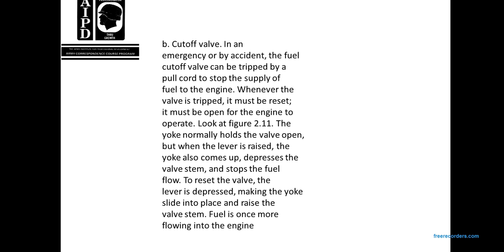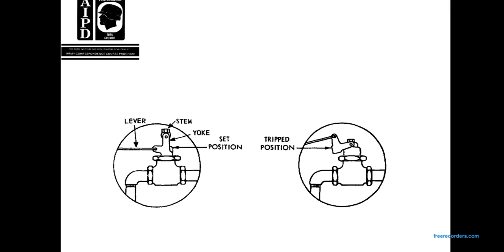Cutoff valve: the emergency cutoff valve can be tripped by pulling the cord to stop the fuel supply to the engine. Whenever the fuel valve is tripped, it must be reset. It must be open for the engine to operate. Looking at figure 2.11, the yoke normally holds the valve open, but when the lever is raised, the yoke will also come up and depress the valve stem. This stops the fuel flow. To reset the valve, the lever is depressed, making the yoke slide into place, raising the valve stem. Fuel is once more flowing into the engine. Here are the lever, stem, yoke, set position and trip position.